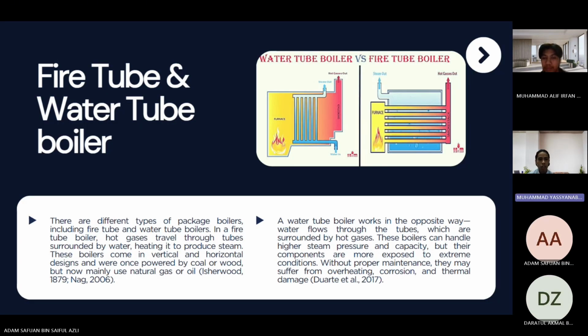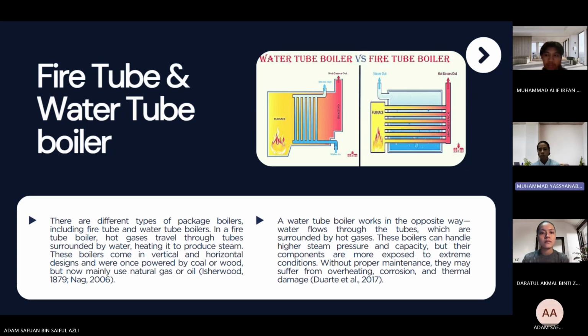Package boilers are fire tube and water tube boilers. There are different types of package boiler, including fire and water tube boilers. In a fire tube boiler, hot gases travel through tubes surrounded by water, heating it to produce steam. These boilers come in vertical and horizontal designs and were once powered by coal or wood, but now mainly use natural gas or oil. A water tube boiler works in the opposite way.